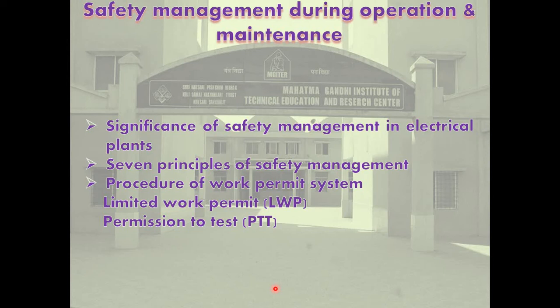As per the recently accepted theory, accidents occur mainly due to lapses of site management and not due to individual mistakes alone. For example, if a person touched a live conductor and got a severe shock, why was he allowed to enter a dangerous zone? Why was the safety permit system not introduced? Why were fence and gate not provided? Why was the live conductor exposed and accessible? Why was the person not trained? Why was the circuit energized from remote when maintenance was in progress? Why was safety earthing not provided? So, the root cause and supporting causes behind an accident are due to management lapse. The individual is a victim.